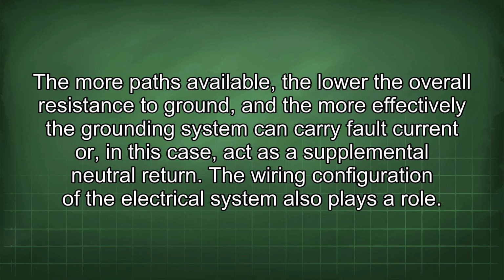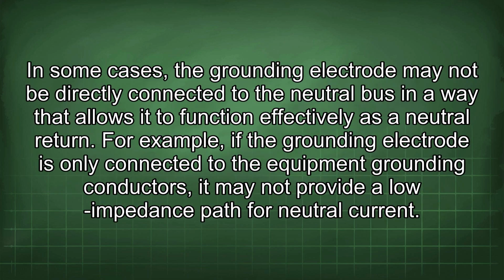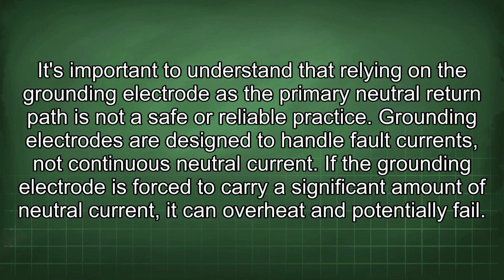The wiring configuration of the electrical system also plays a role. In some cases, the grounding electrode may not be directly connected to the neutral bus in a way that allows it to function effectively as a neutral return. For example, if the grounding electrode is only connected to the equipment grounding conductors, it may not provide a low impedance path for neutral current. It's important to understand that relying on the grounding electrode as the primary neutral return path is not a safe or reliable practice. Grounding electrodes are designed to handle fault currents, not continuous neutral current.